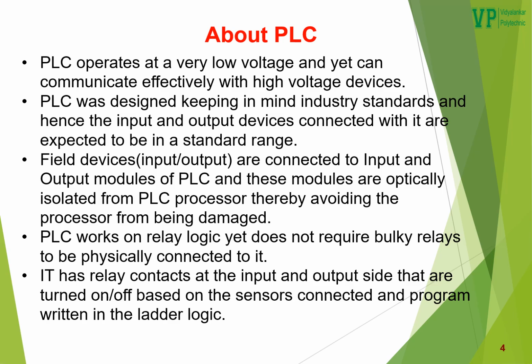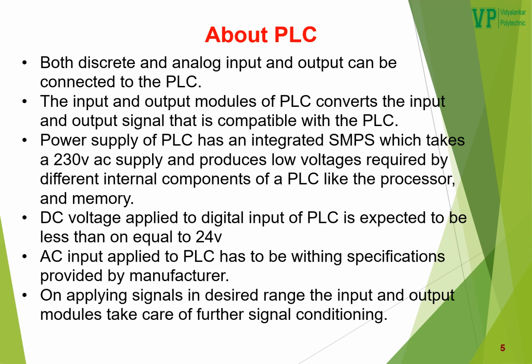PLC works on relay logic, yet it does not require bulky relays to be physically connected to it. It has relay contacts at the input and output side that are turned on and off based on the sensors connected and the program written in ladder logic. Both discrete and analog input and output can be connected to the PLC. The input and output modules of the PLC convert the input and output signals to a form that is compatible with the PLC.